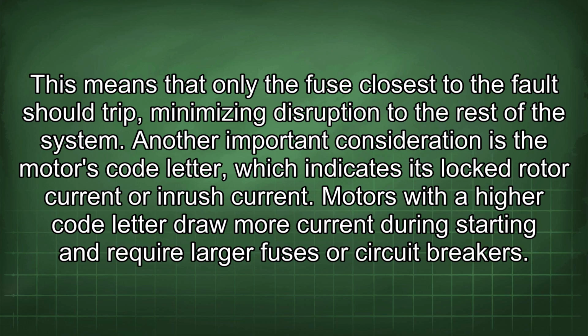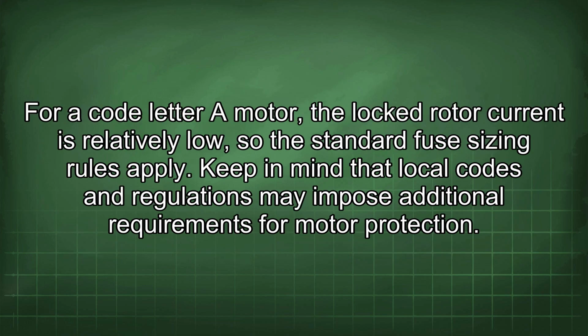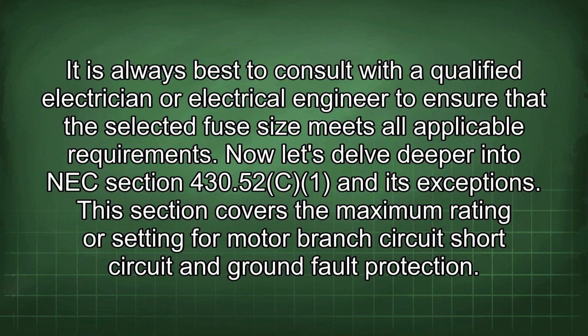Another important consideration is the motor's code letter, which indicates its locked rotor current or inrush current. Motors with a higher code letter draw more current during starting and require larger fuses or circuit breakers. For a code letter A motor, the locked rotor current is relatively low, so the standard fuse sizing rules apply. Keep in mind that local codes and regulations may impose additional requirements for motor protection. It is always best to consult with a qualified electrician or electrical engineer to ensure that the selected fuse size meets all applicable requirements. Now let's delve deeper into NEC section 430.52(C)(1) and its exceptions.